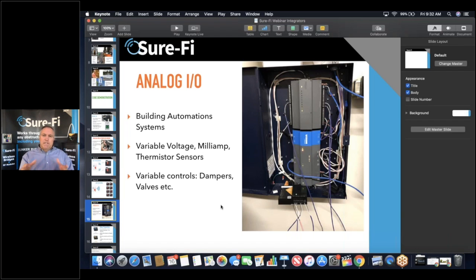So you guys know you put out a JACE unit. Sometimes you have to put those out geographically, and you have maybe 7 or 8 JACE units out there because geographically you've got to run those sensors in. You're limited by how far the wire can go before you turn it into network wire, right? But those also have service contracts on them. You're never filling up all the I/O until you get back to the controller side. And so what you can do is more efficiently use your JACE units.